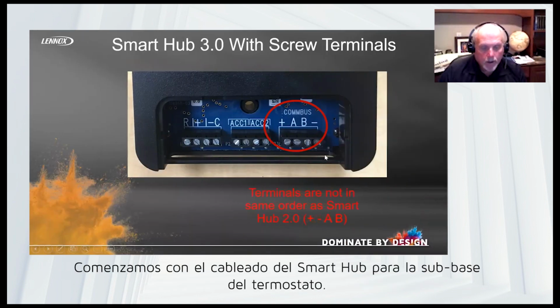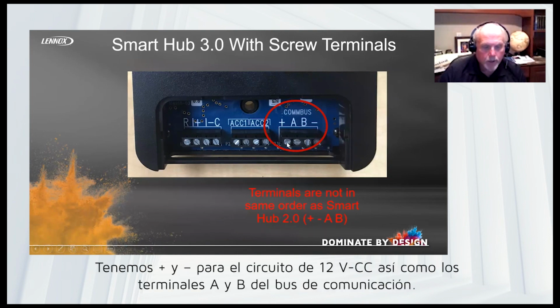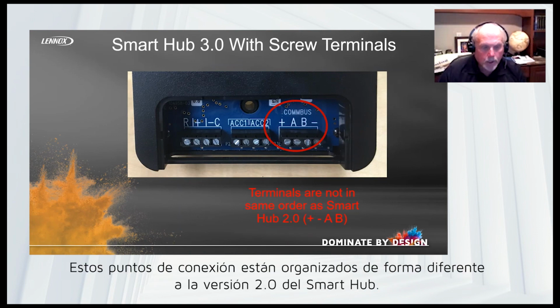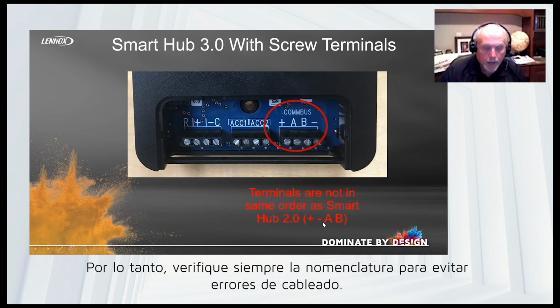Starting over here with our wiring to our sub base for our display, like I said, we have our plus and we have our minus. That is our 12-volt DC circuit. And our A and B are our communication bus. This is arranged a little different from the 2.0 Smart Hub, as those terminals were lined up like down here. We had plus, minus, and A and B. So as long as you're looking at your nomenclature, you should have no issue wiring it up. Plus and minus is your 12-volt DC circuit. A and B is your communication bus.